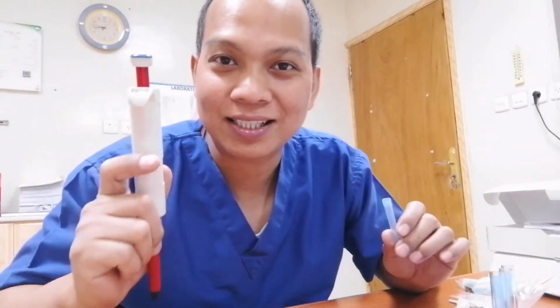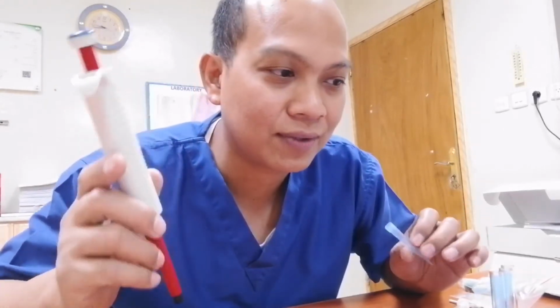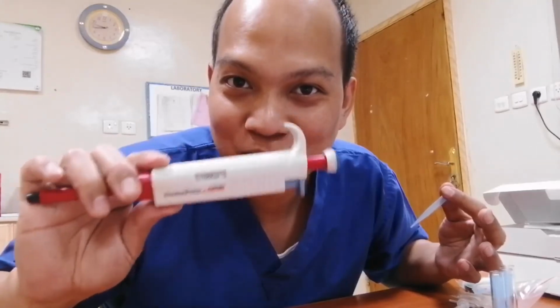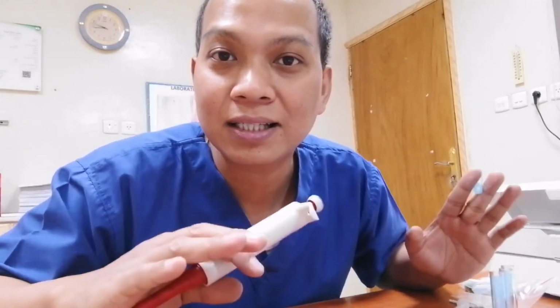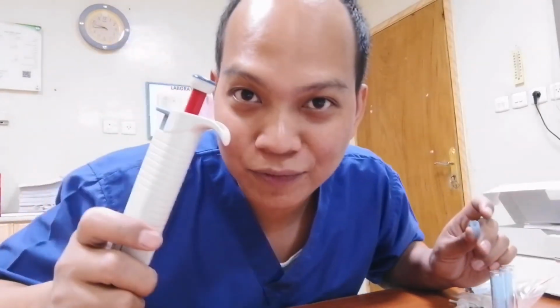So again guys, thank you for watching. I hope that it helps you, especially those working in a laboratory who have doubts about their pipettes. Okay, so calibration is the key. You have to calibrate based on the clinical laboratory standards. Pipettes should be calibrated within 3 months to 6 months, but for me, I do calibration every month. Who knows, this pipette may fall down and it will also affect it. If this pipette falls every time, it can make a big difference. Okay, so take care of your pipette.